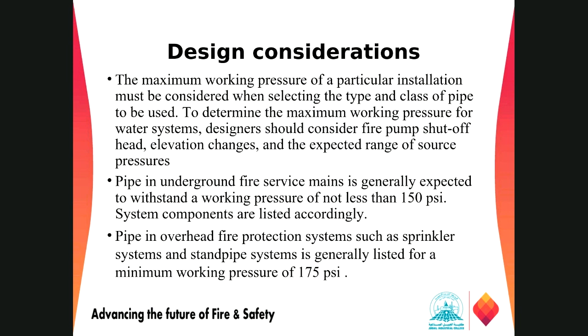If we have a pressure reducing valve, it is intended to protect components from both high static and flowing pressures. So sometimes we have to use a pressure reducing valve in the building. If the building height is more than normal, if it is around 40 or 50 floors and we need more pressure, maybe 24 bar or higher than that, maybe 40 bar, then we need pressure reducing valves in those conditions in some zones.